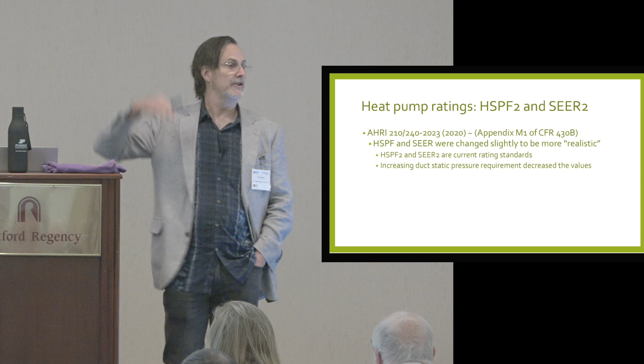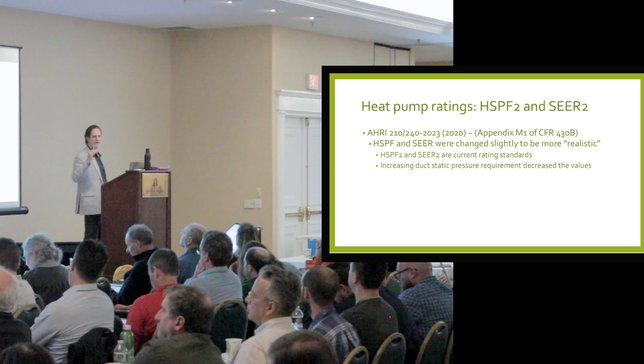in the test. But they previously had used a very low static pressure for a residential duct system of 0.2 inches of water, which if anyone here has ever tried to design a system that actually works at 0.2, it's not easy to do. And if you've ever looked at actual equipment in the field that HVAC contractors install, you never see it operating that low. So they increased the static pressure during the test. That made the units a little bit less efficient because they have to use more fan energy to move the heat either in or out, so that both HSPF 2 and SEER 2 numbers went down.